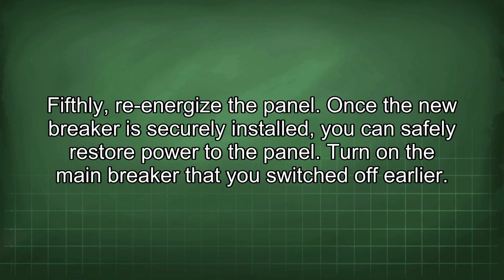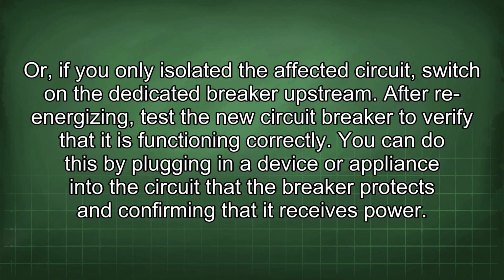Fifthly, re-energize the panel. Once the new breaker is securely installed, you can safely restore power to the panel. Turn on the main breaker that you switched off earlier. Or, if you only isolated the affected circuit, switch on the dedicated breaker upstream. After re-energizing, test the new circuit breaker to verify that it is functioning correctly.